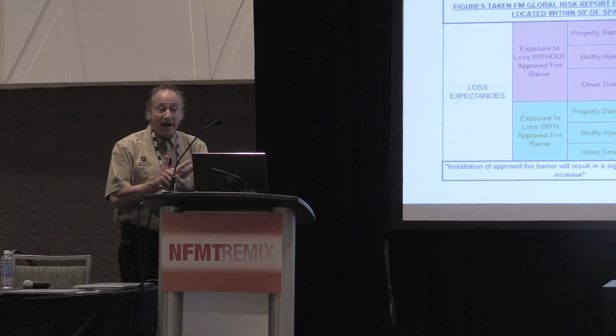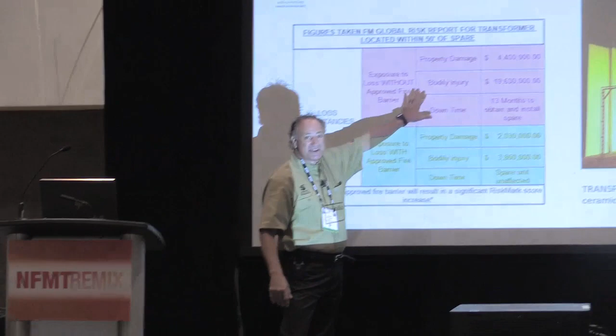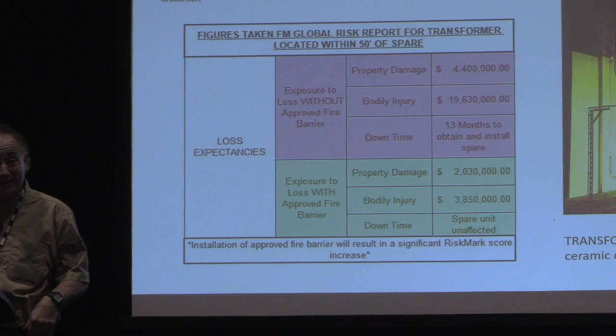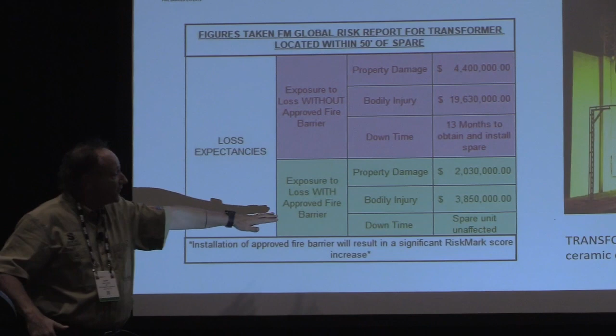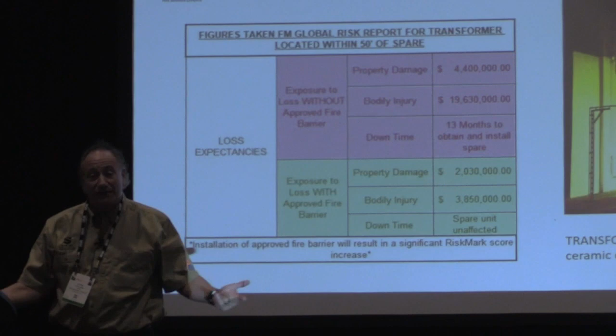So it's not just industrial operations, but we're going to talk a little bit about the impact of insurance and if you did lose power and why the insurance companies have identified transformers and power that's coming into your facilities as a critical asset. The amount of money lost and property damage without a transformer fire barrier system, easily you can see big numbers. 13 months of downtime on average. These are Factory Mutual numbers, okay? These are talking about all the transformer failures. This is what we're feeling. With fire barrier systems, these numbers drop. And this is what you're rated on for your insurance.